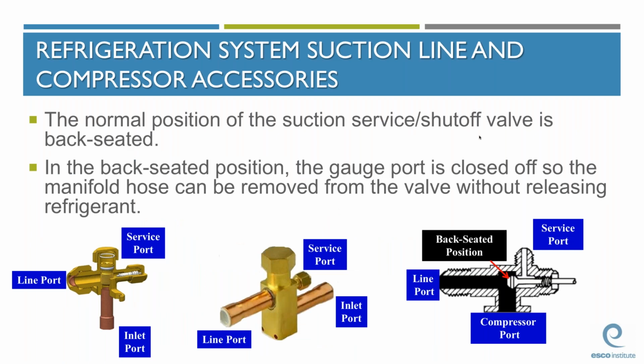Service valves are also classified as system accessories. It's important for your students to know the types of service valves as well as the various positions they can be placed in. We are referring to the positions of back-seated, front-seated, mid-seated, and cracked off the back seat. Stress to your students that the normal operating position of suction or liquid service valves is back-seated, and it's only in this back-seated position that the gauge port is closed off so the manifold hose can be removed from the valve without releasing system refrigerant.